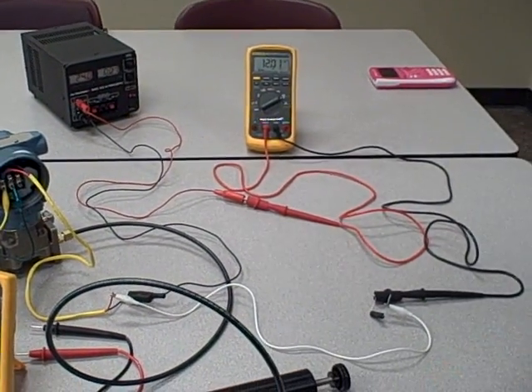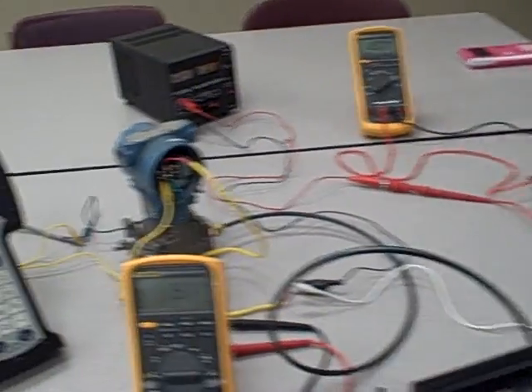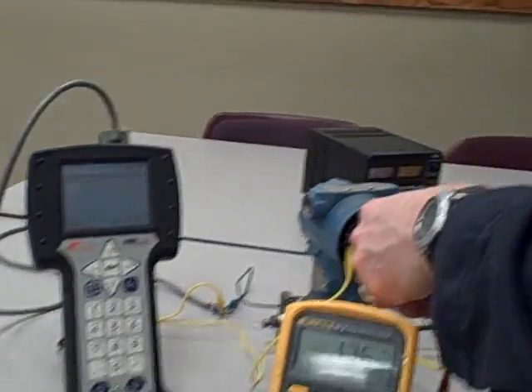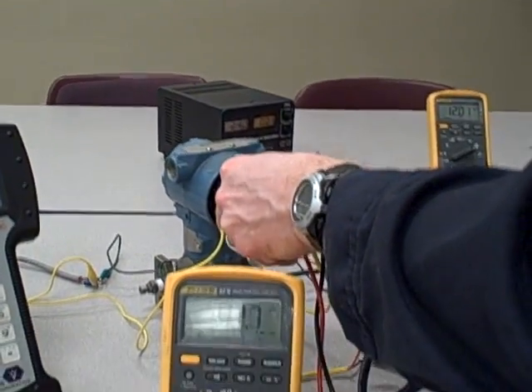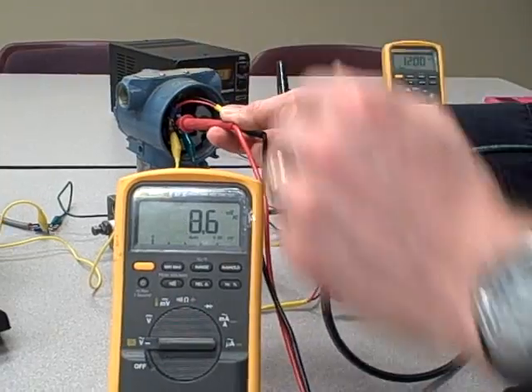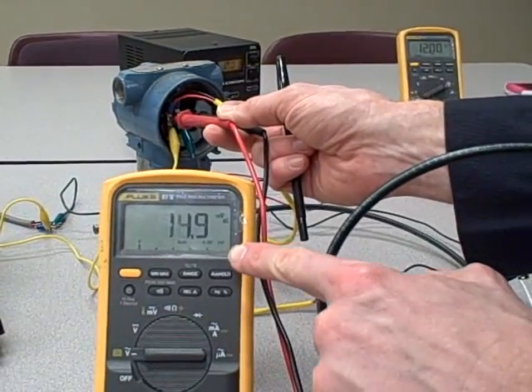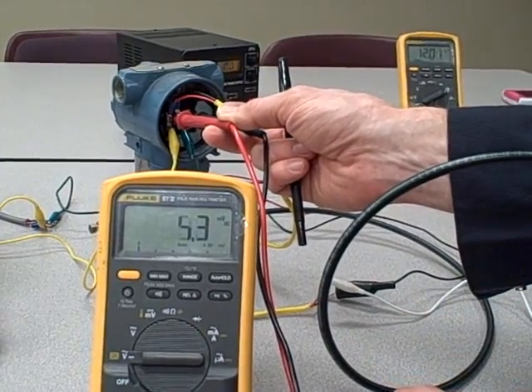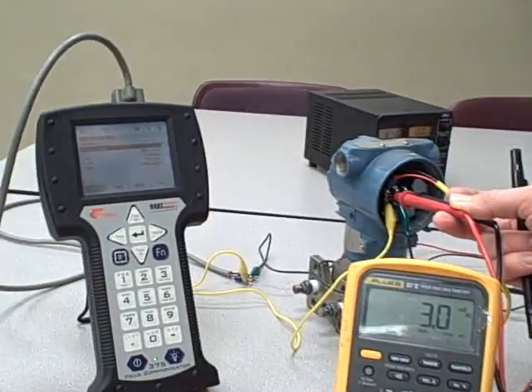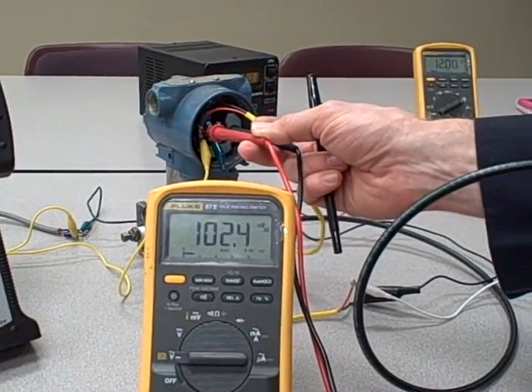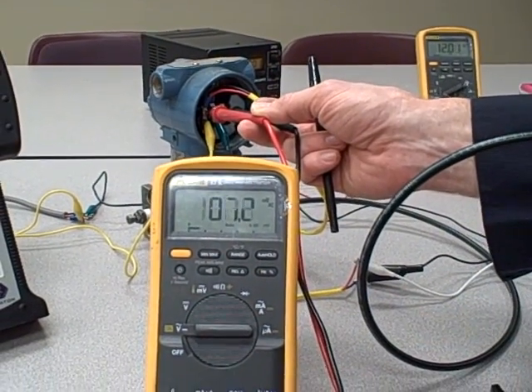That is why a loop resistor is necessary for HART communication to take place. So now, as I look at my AC millivoltage across the transmitter terminals, and I press the retry button, now we see the voltage reappear, and it's communicating once more.